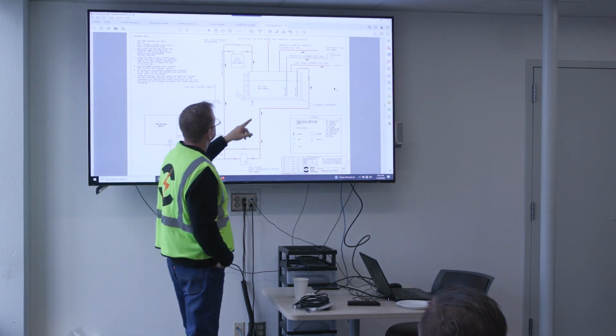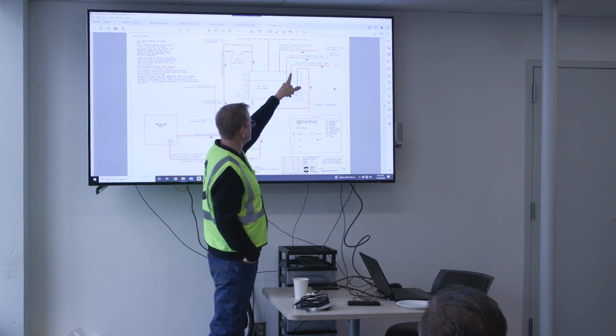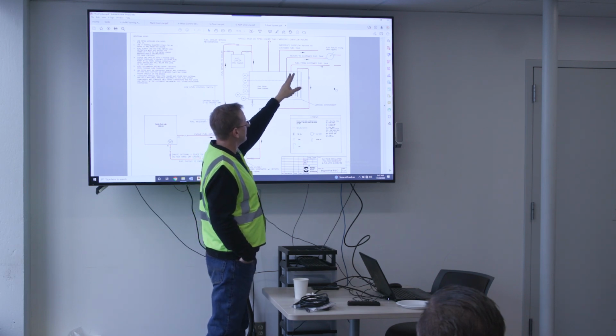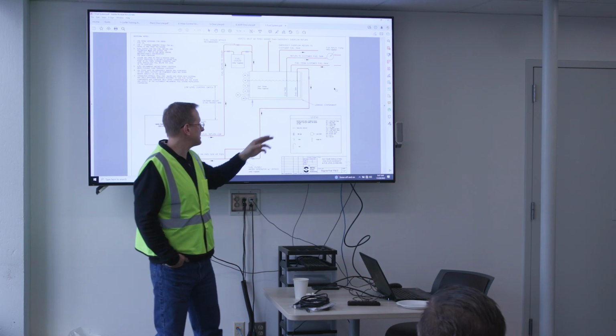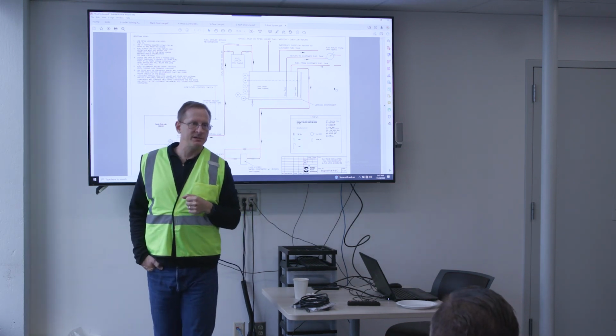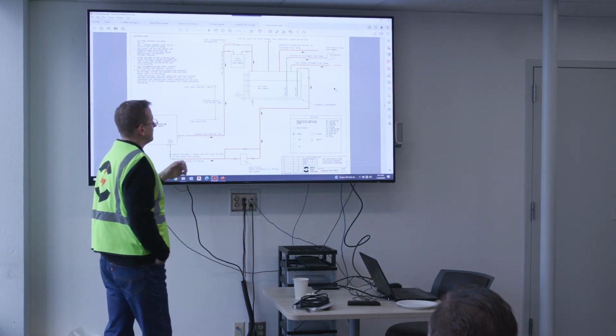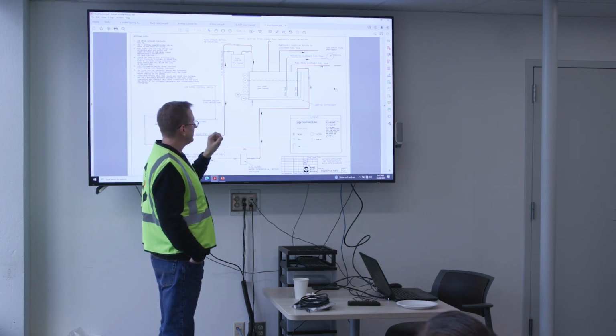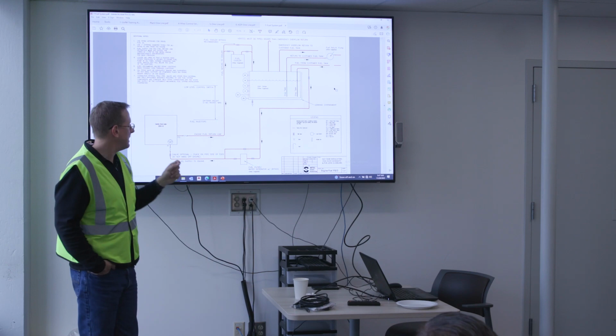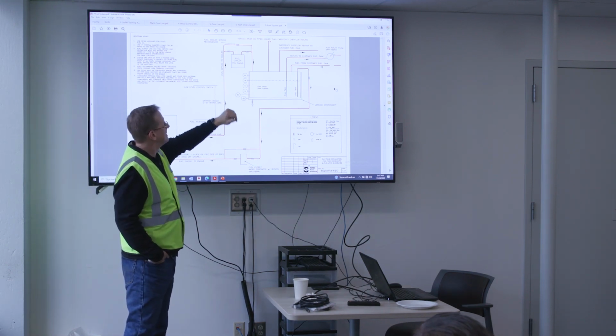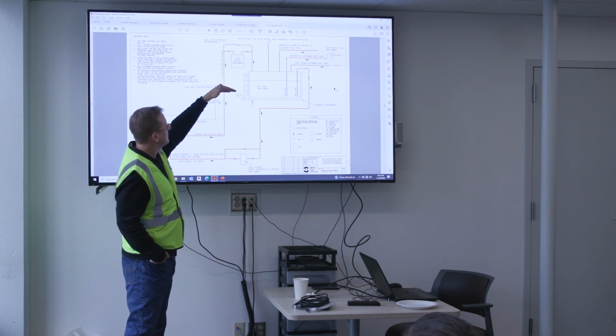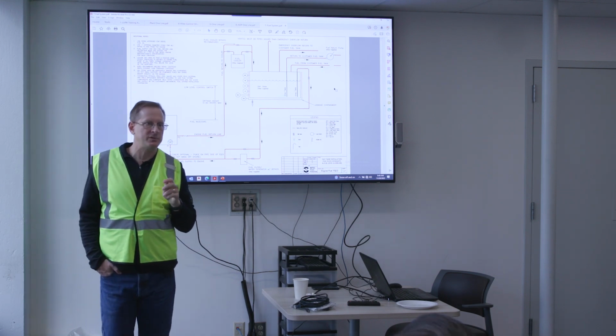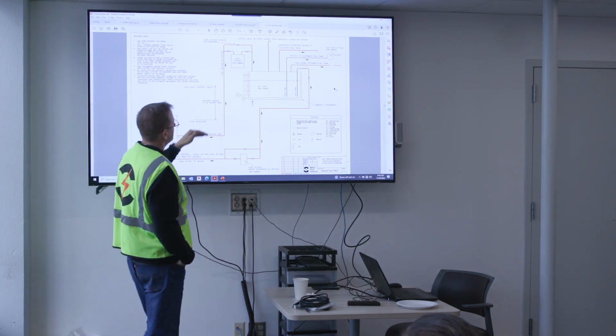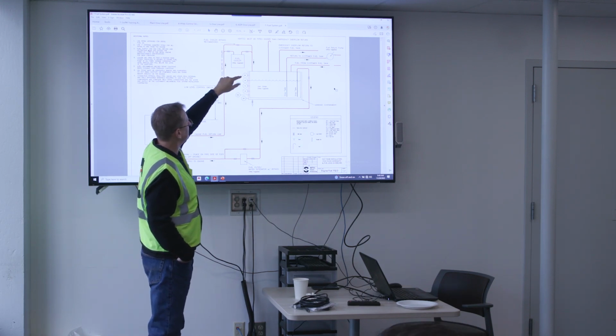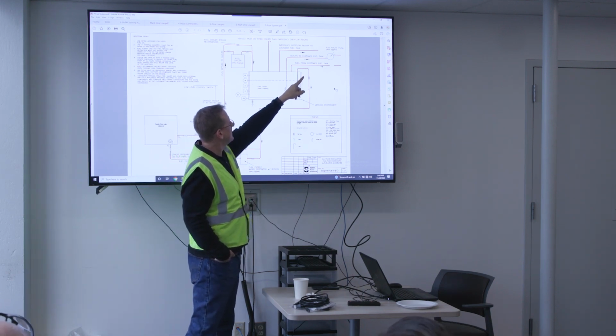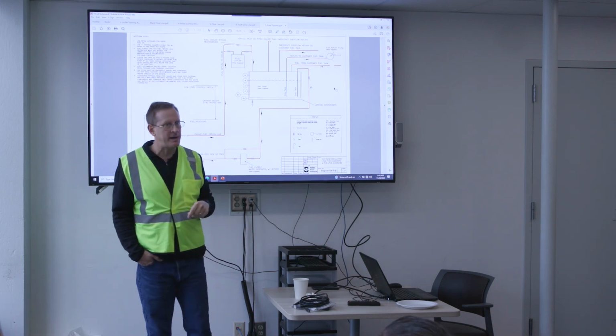Okay, so there's a line coming into the tanks through some valves that call for fuel from your bulk storage, or there are actually some solenoid valves that will open and pressurize your system when the tank is calling for fuel. And that's all controlled by the tank itself and its own fuel control panel. The only interaction the tank has with our PLC is, again, to control the fuel cooler and also to give us alarms when we hit a low level or critical low, or we see some sort of a leak detect in the interstitial space of the day tank itself. Also, if the level of the day tank gets to what we call a critical high level, it will actually turn on a return pump, and it'll start pumping fuel from the day tank back into your main storage.